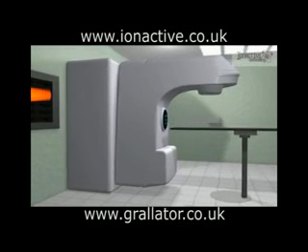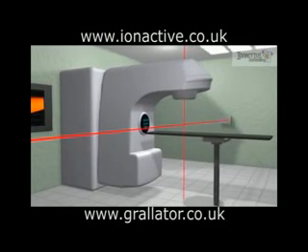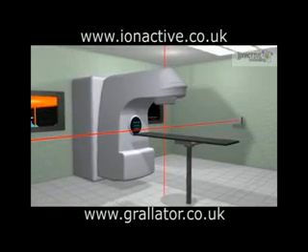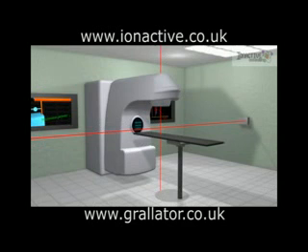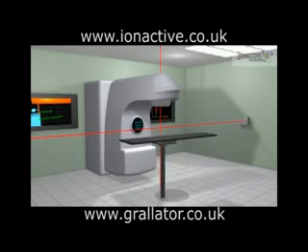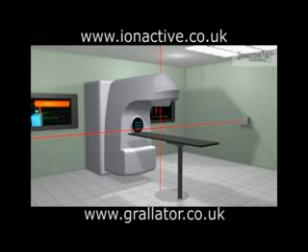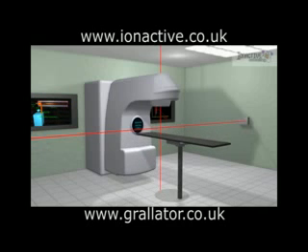The dose delivered by a LINAC is centred on a point called the isocentre, and mechanisms are required to accurately position the target or patient on these. For the medical LINAC, a patient couch is used that has many degrees of freedom. The couch is supported by a pillar mounted in a revolving base. It can be raised or lowered and can itself revolve around the pillar. In addition, it can also slide left and right and forwards and backwards, so providing flexible positioning of the patient.